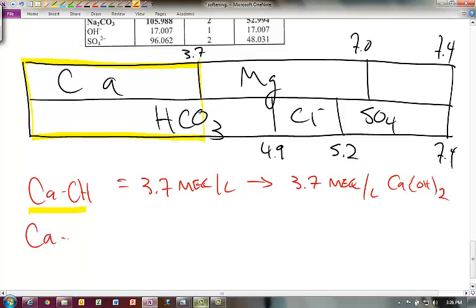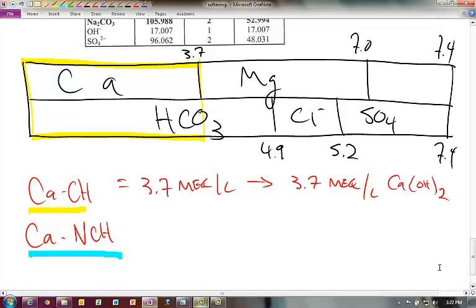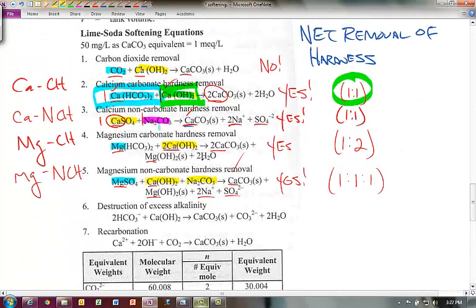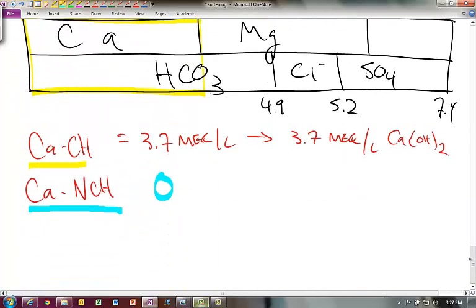Now looking at calcium non-carbonate hardness. Looking at the bar diagram, it doesn't appear that we have any calcium non-carbonate hardness — all the calcium is complexed with the carbonate. So we'll put zero for that. If we did have some, it would be a one-to-one relationship and we'd need to add soda ash rather than lime slurry.